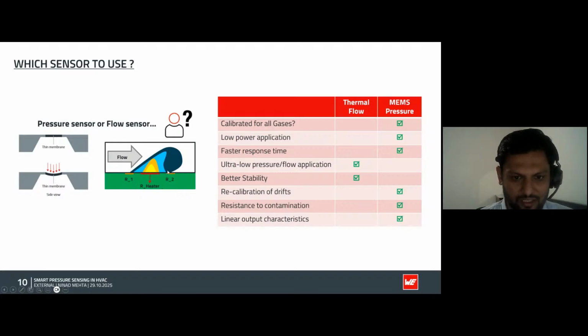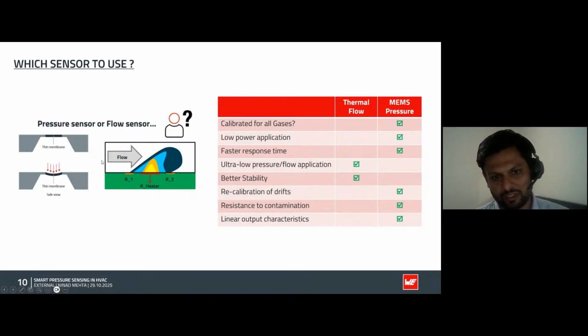And on the right-hand side is another principle, where you are measuring the flow. Modern flow-based sensors use a small heating element or a very small heating coil, and there are two temperature-dependent resistors. When the airflow passes over the heating element, the hot air disperses, and one resistor and the other resistor will have different values, and based on that we can calculate how much flow there is in the flow-based sensor.